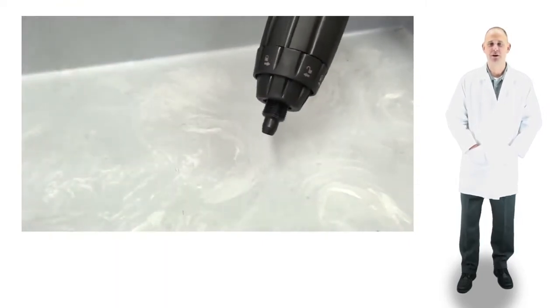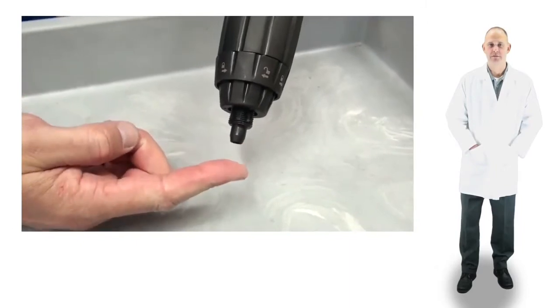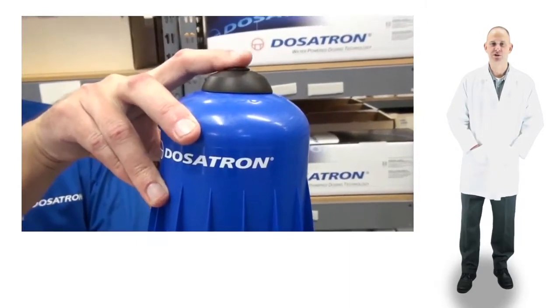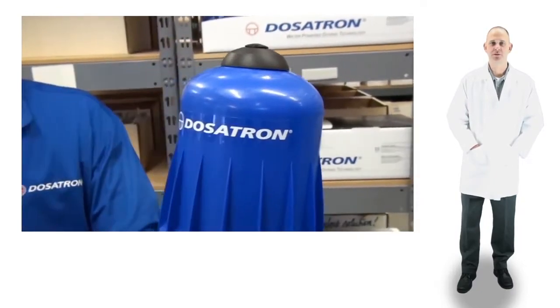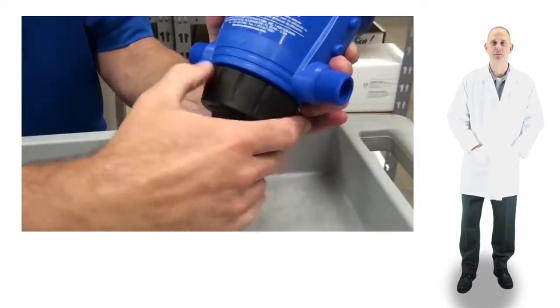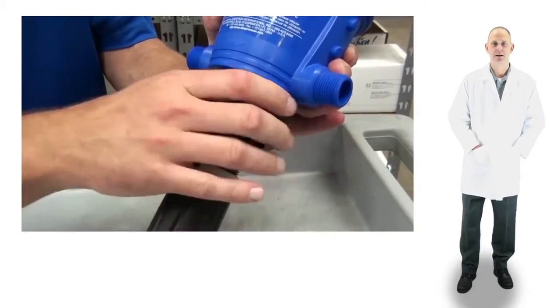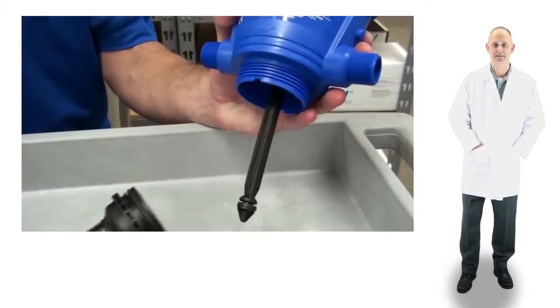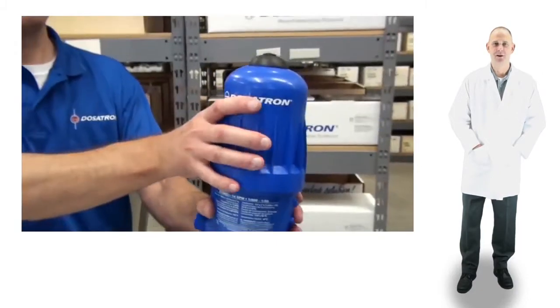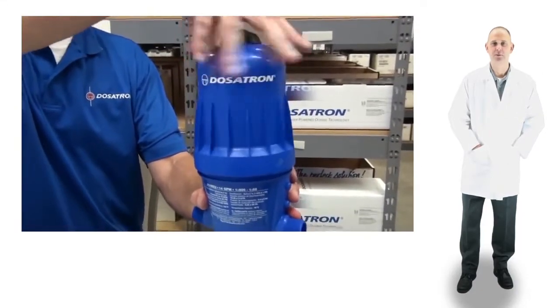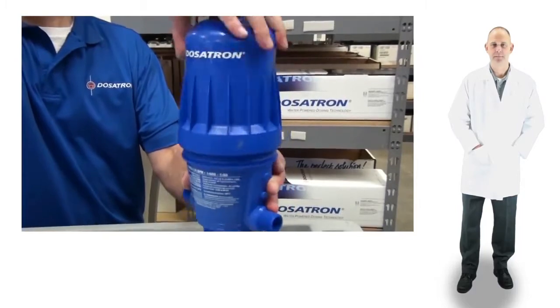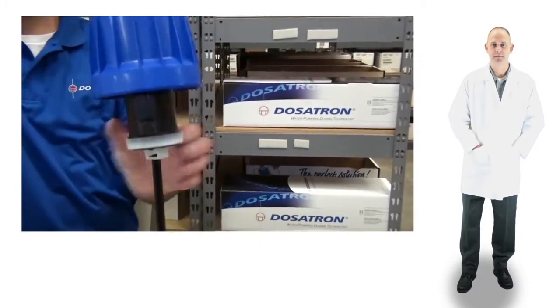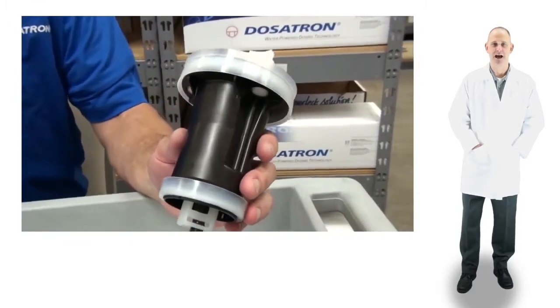If you don't feel suction on your finger, turn the water off, release pressure by pressing the air bleed button and remove the Dosatron. Unscrew the injection stem nut and pull the stem straight out from the body. Set the nut and stem aside. Unscrew and remove the bell housing and pull the piston out of the body. Set the bell housing and body aside.